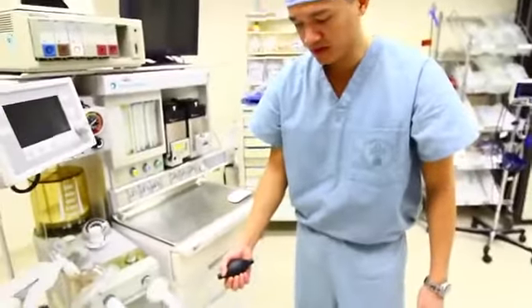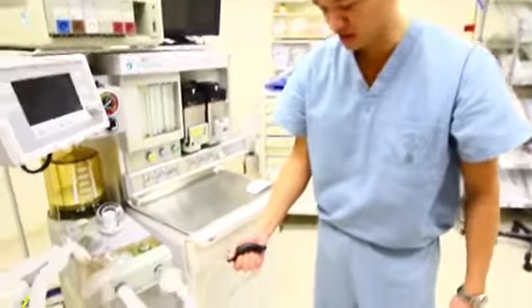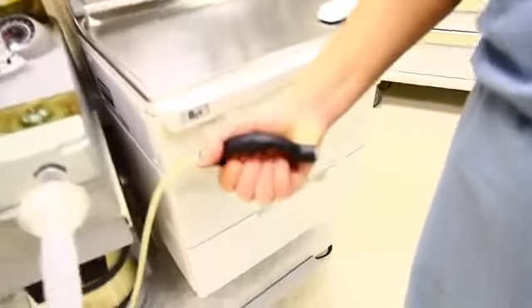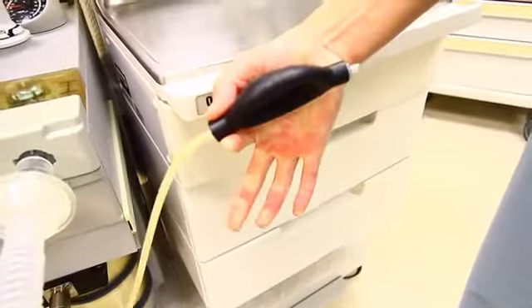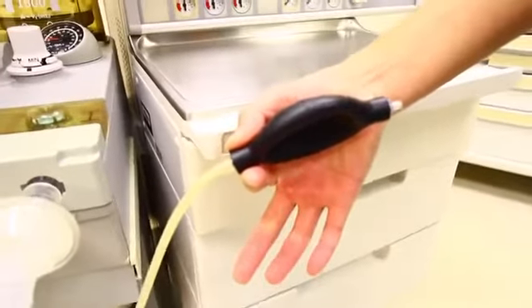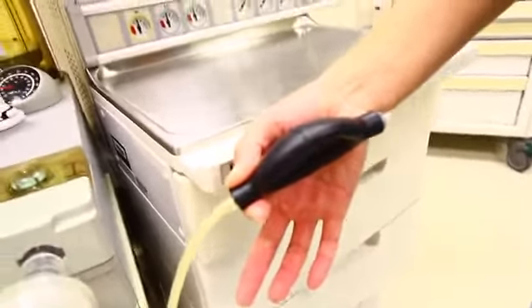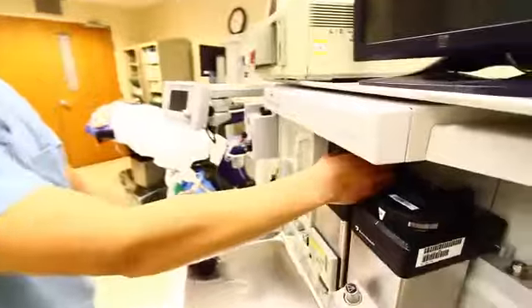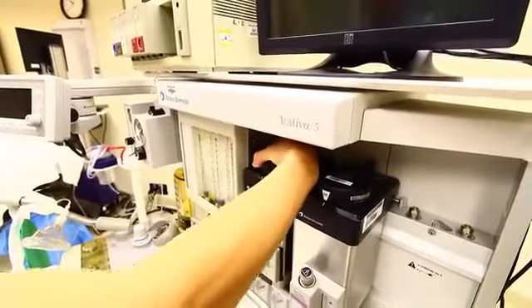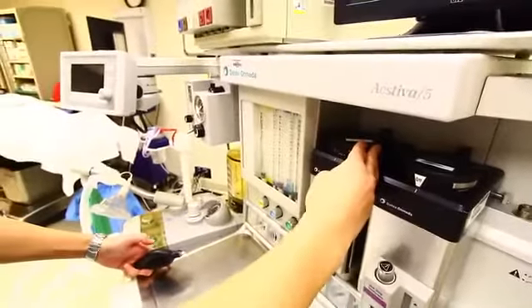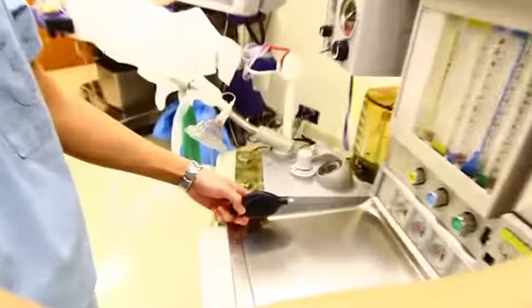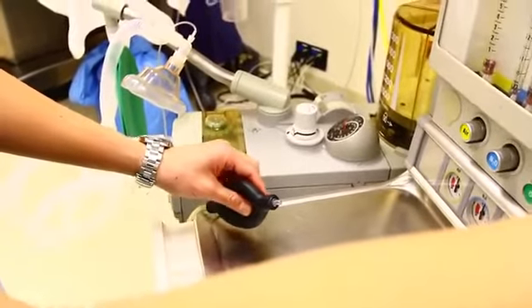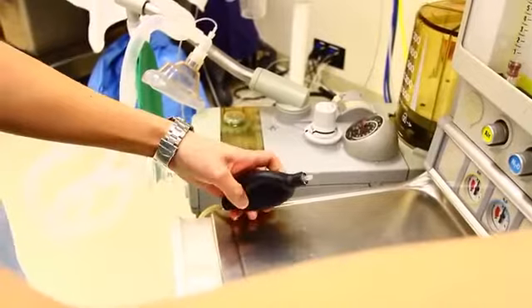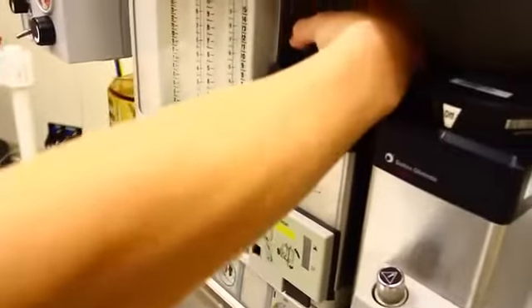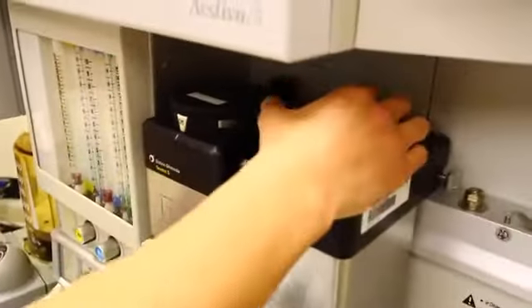Now you want to squeeze the bulb repeatedly until it becomes flattened. Now that you notice it's flattened, you want to ensure that it stays collapsed for 10 seconds at least. Now open each vaporizer one at a time. Sometimes you'll notice the suction bulb will lose its vacuum, so you'll need to squeeze the bulb until it's collapsed. Now repeat the previous steps for each consecutive vaporizer.